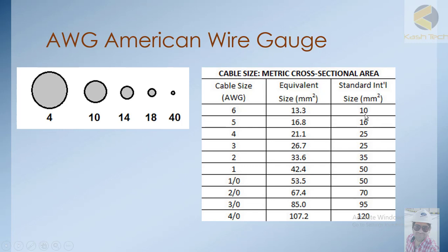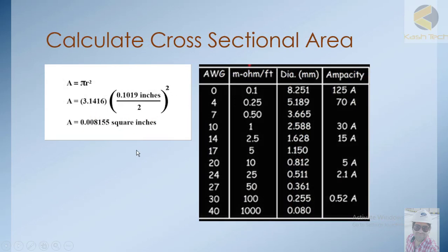AWG 6 is equivalent to 13.3 mm² while the closest international standard size is 10 mm². AWG 5 is equal to 16.8 mm², with the nearest international size being 16 mm². Internationally, cables are available in standard sizes: 10, 16, 25, 35, 50, 70 mm² and so on.